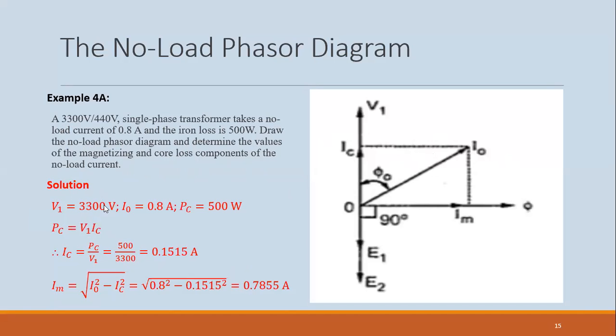V1 is equal to 3,300 volts. I0, the no load current, is equal to 0.8 amps. Notice how small that is — look at the high voltage, 3,300 volts, and it just pushes 0.8 amps through the primary winding on no load. I think when we're in the lab, the current probably won't go more than 1 amp, somewhere around there.